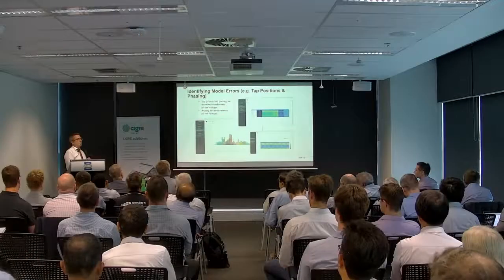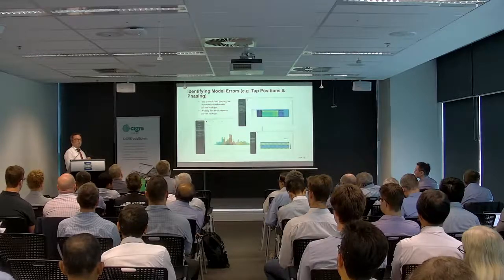Especially in the case of Energix, where we had downstream LV measurements of 30% of the distribution transformers, we were able to correct things like phasing and detect wrong tap positions. As measurements further down in the LV get more available, probably soon from customers, these functions can help reveal quality problems in the LV network models, and state estimation can guide you to where the errors are.